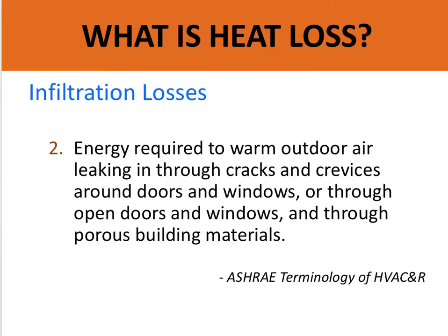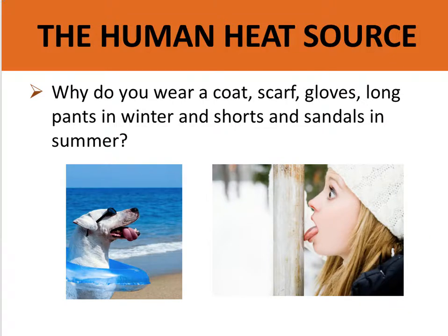Infiltration loss is the energy that's required to warm the outdoor air, if it's cold, that's leaking in through cracks and crevices around every single door, window, or through open doors or windows, and through the porous building materials. Feel around an electrical outlet on an outside wall on a cold day. A lot of times you'll feel cool air. That's actually heat leaving the building. That's infiltration loss.